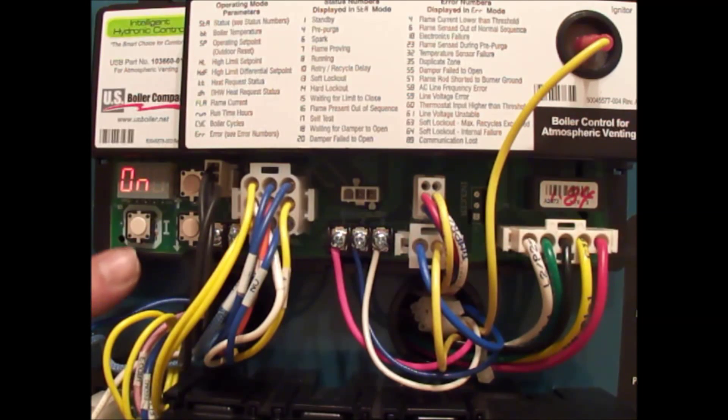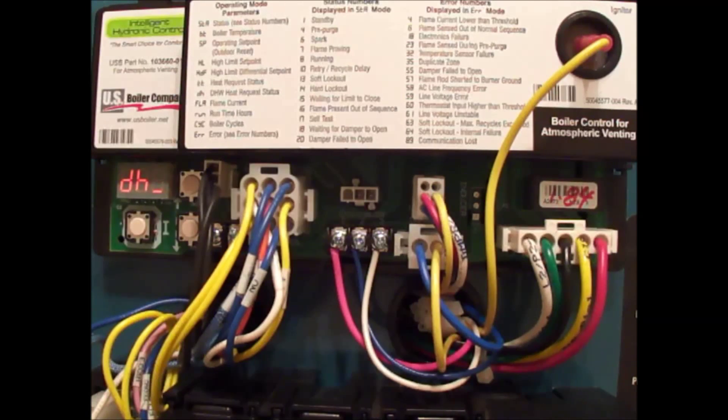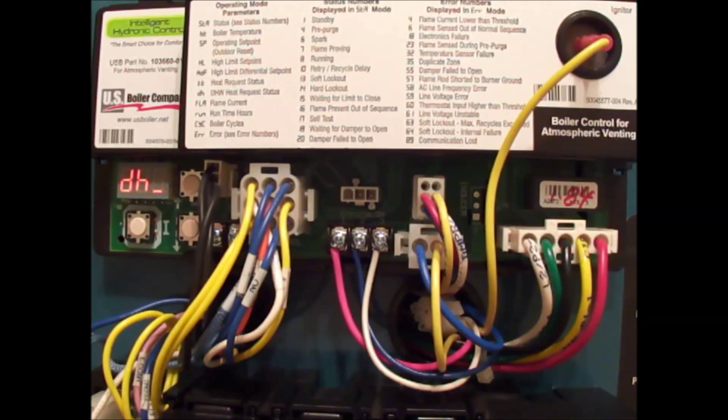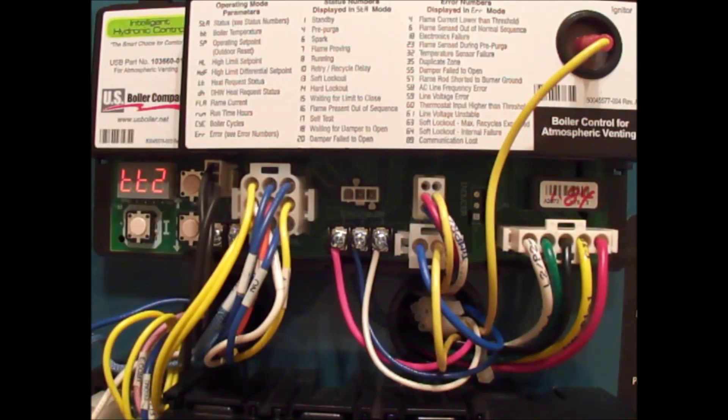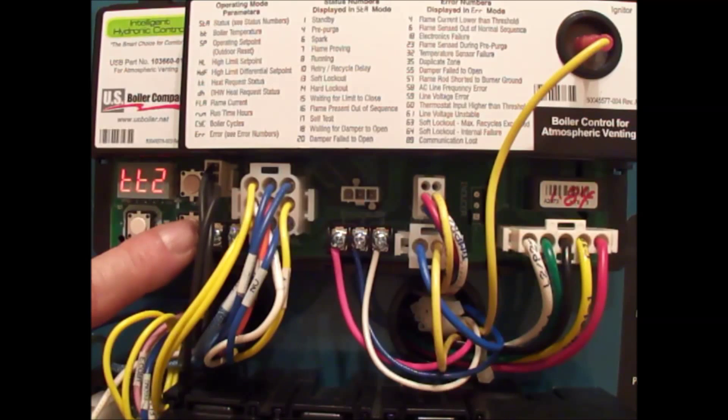If you make this second zone instead of domestic hot water, if you make it heat, it ignores priority. We can change that to domestic hot water or TT2. TT2 is your second zone of heat. This control can do two inputs—it can be two heat zones, or one heat zone and one domestic hot water. If we leave it in DH then it would not ignore priority and it would shut down the heating pump.